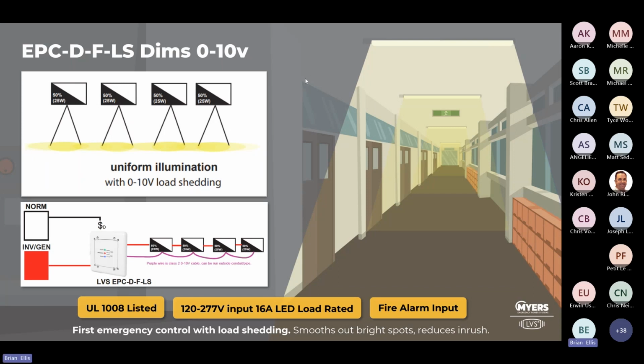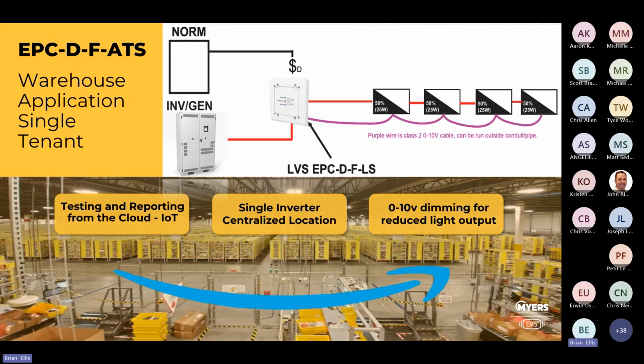Nice little graphic here. Okay, so applications where this might work. One thing I think about is the warehouse application. So if the warehouse is everything completely open and there's no shelving or anything like that, then from a wiring perspective, it may be better to provide battery packs, if I'm honest with you. One of the big issues with battery packs we all know is, who's our customer? A contractor might want to just be off the job in a year, but our true clients, right, the end user, do they really want to swap out battery packs and 280 fixtures in a warehouse when they start to fail? No, they'd rather have a central inverter in one place, automatic testing, swap out the batteries every 10 to 20 years, right? So there is definitely a place for the inverter, but we have to make sure that it's in the right price point for us to supply it.